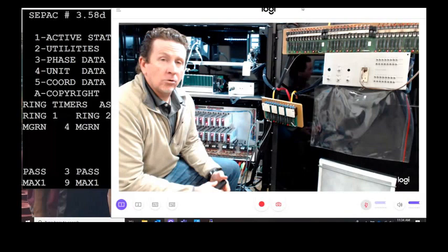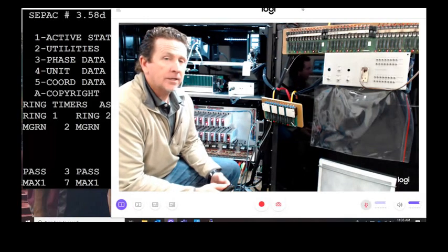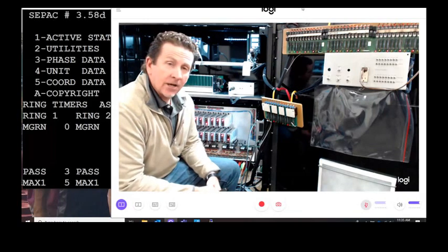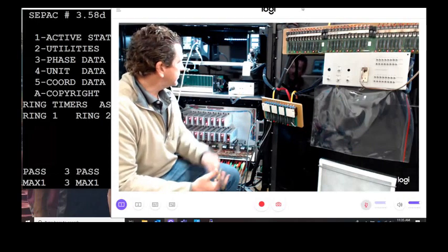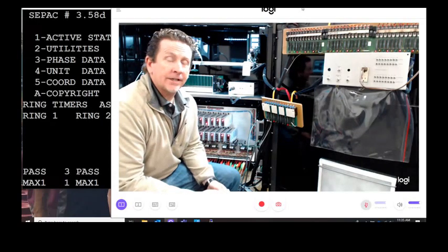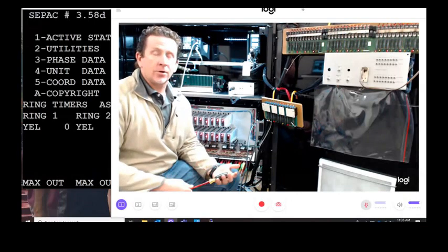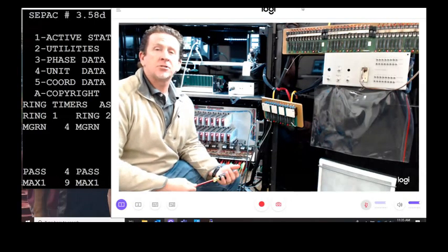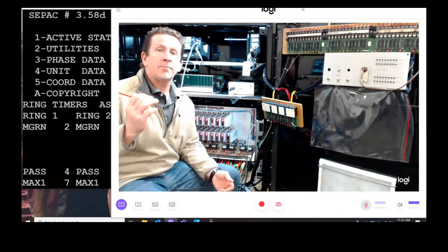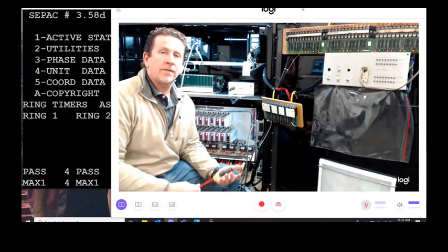And I'll say, go look at your power supply. And they look at it and tell me the LED is out. So basically, I'll say, that ties to your LED circuit. It's its only purpose in life. So that either burned out on the controller, or commonly you just blew the fuse because you had a short in a button or out in the field, and that blew the fuse.